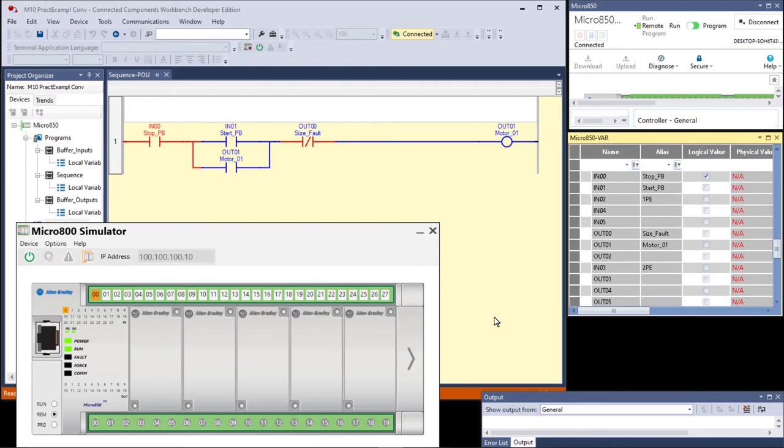And again, we emphasized that earlier in lab projects that you need to get your thinking straight, that these instructions read memory locations, not field devices. They don't read push buttons. They read memory bits that are controlled by the state of the push buttons in the field wiring connected to the screw terminals going through the opto-isolator being collected up and placed in memory.